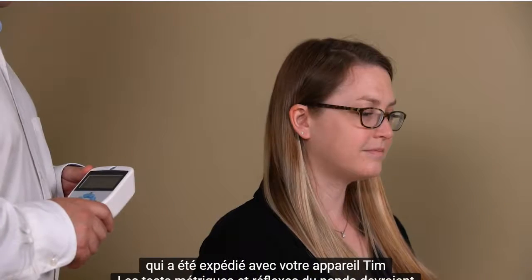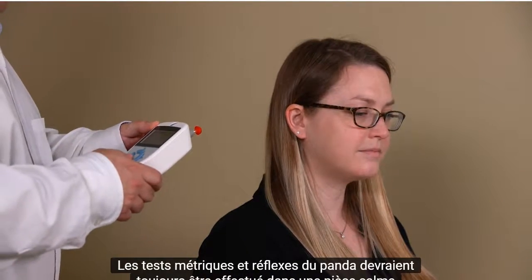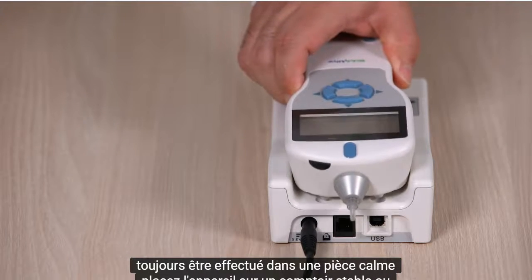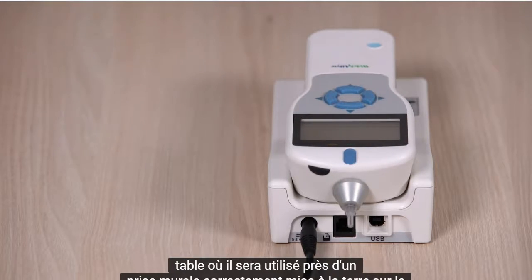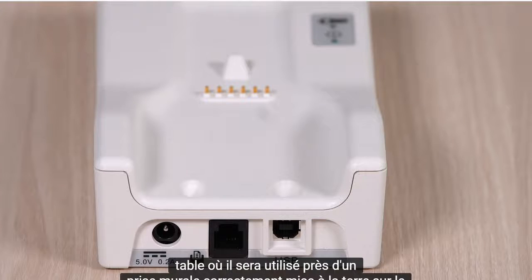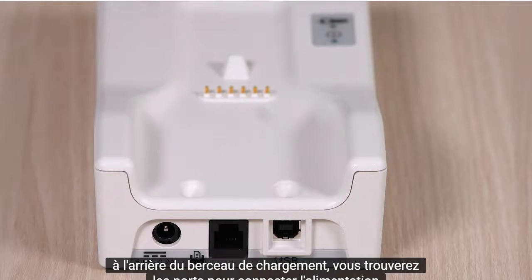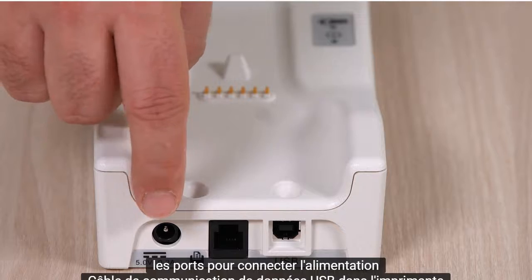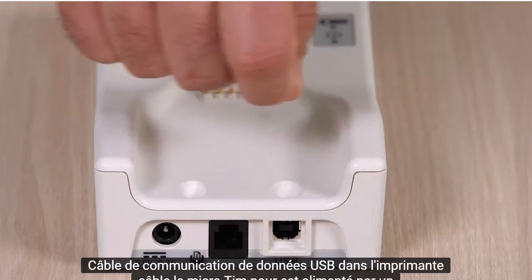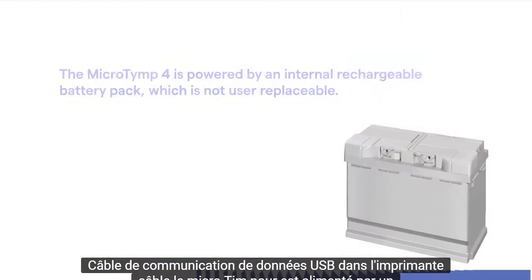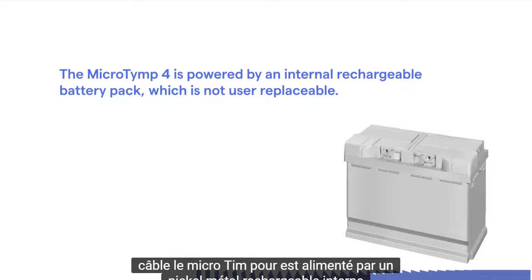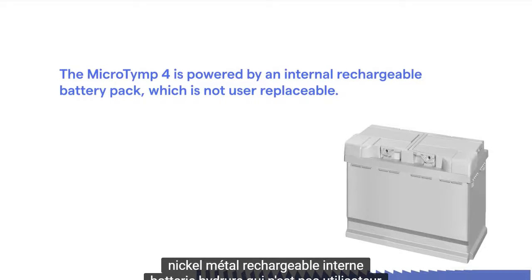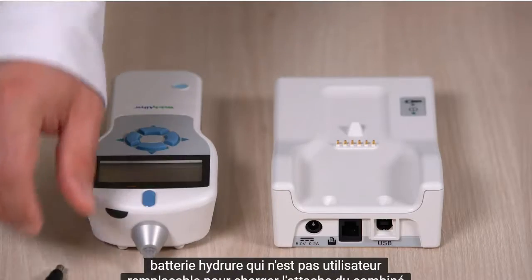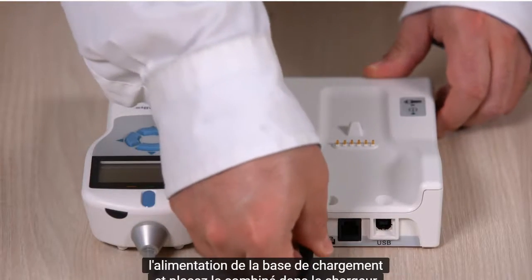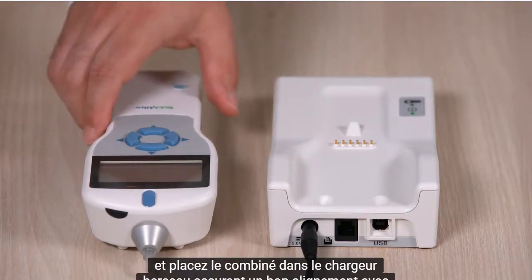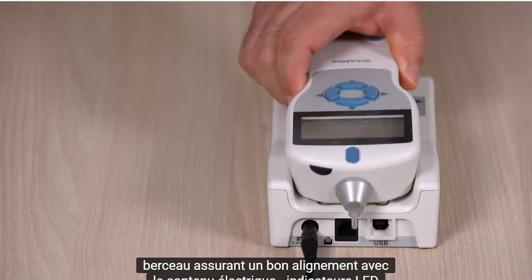Tympanometric and reflex testing should always be performed in a quiet room. Place the device on a stable counter or table where it will be used near a properly grounded wall outlet. On the back of the charging cradle, you'll find the ports for attaching the power supply, USB data communication cable, and printer cable. The MicroTymp 4 is powered by an internal rechargeable nickel metal hydride battery pack, which is not user replaceable. To charge the handset, attach the power supply to the charging cradle and place the handset into the charging cradle, ensuring proper alignment with the electrical contacts.